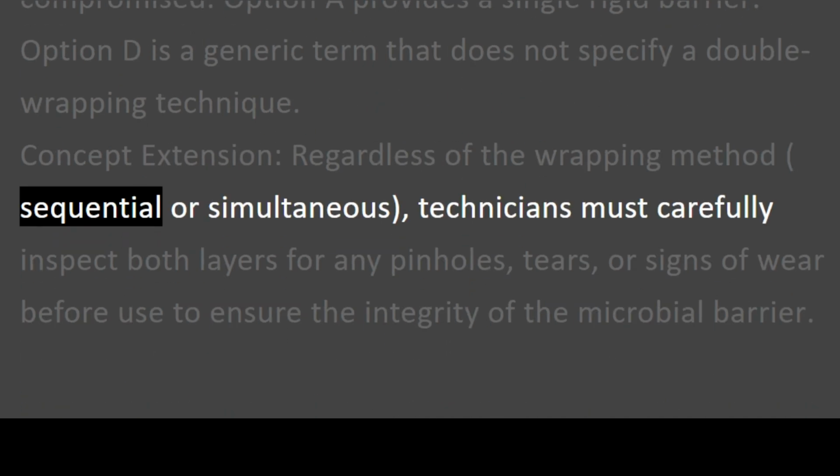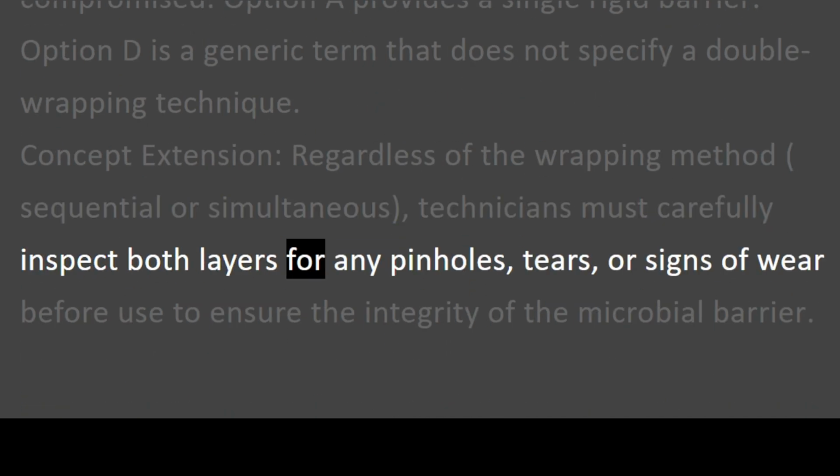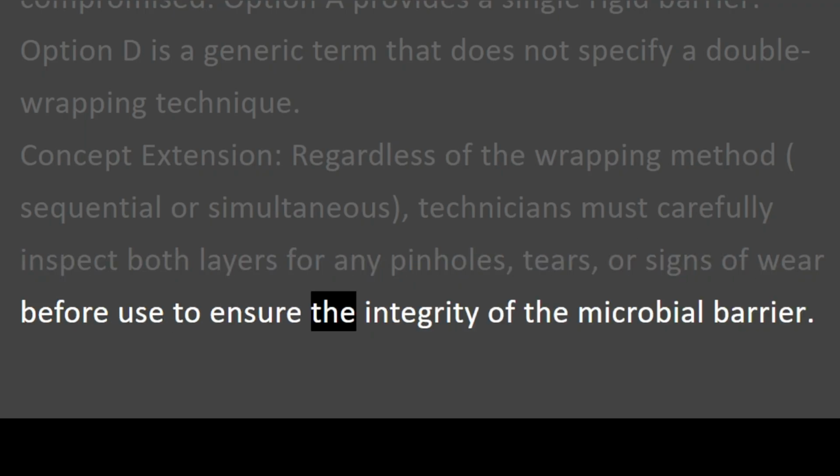Concept extension. Regardless of the wrapping method, sequential or simultaneous, technicians must carefully inspect both layers for any pinholes, tears, or signs of wear before use to ensure the integrity of the microbial barrier.